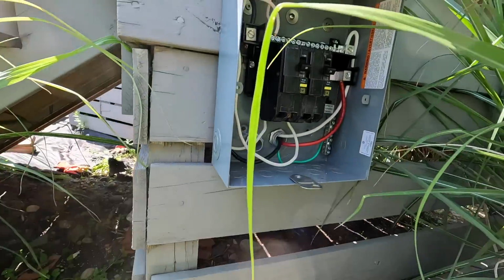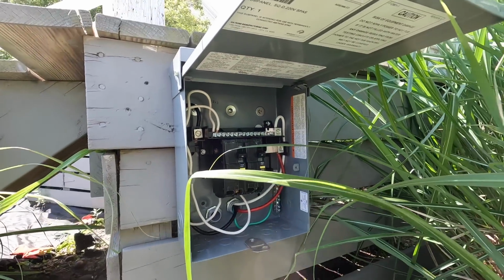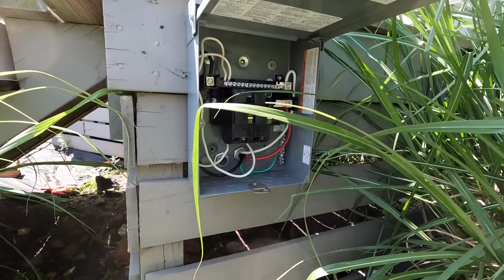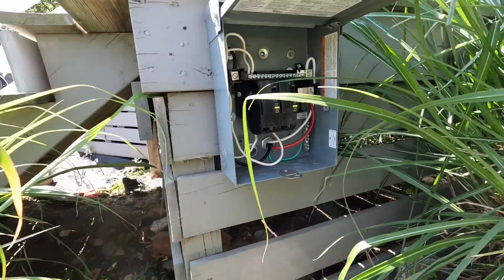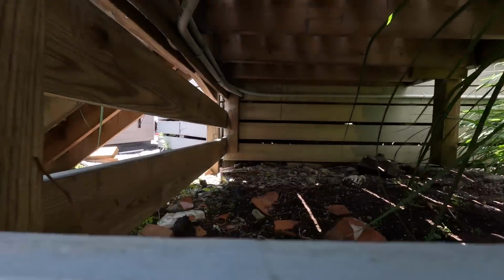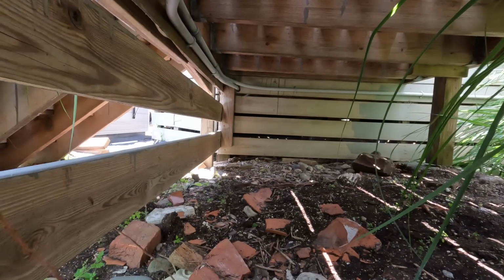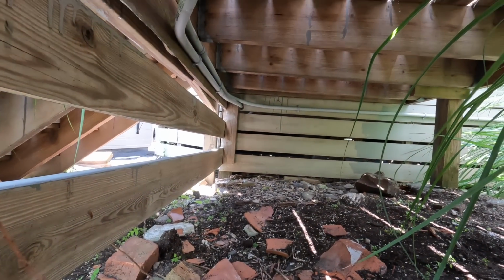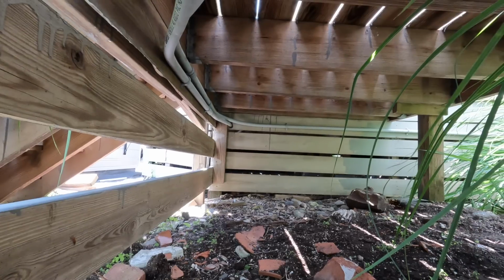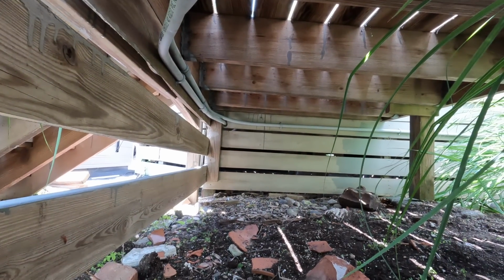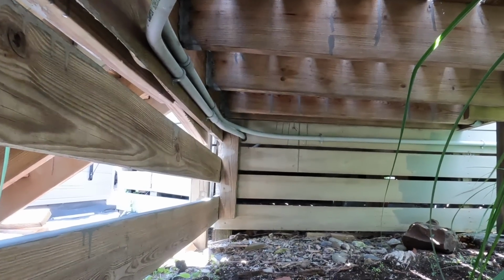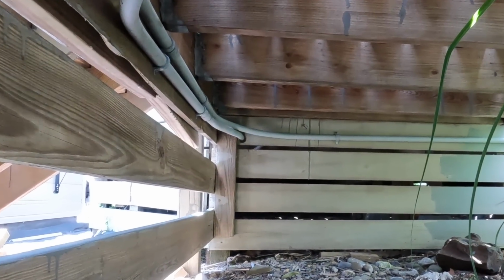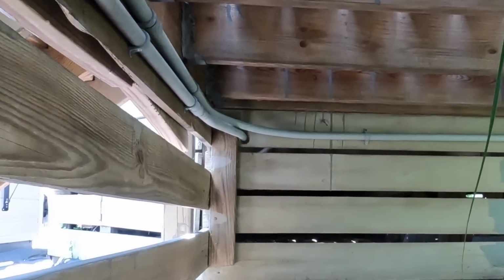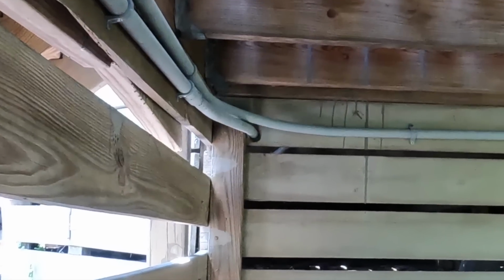Here's my main lug only panel that came with the hot tub assembly. It has a double pole 30 circuit and a double pole 20 circuit, and both of these circuit breakers are GFCIs. This is underneath the staircase. There's some of the conduit that I ran that I did not film. The lower conduit is what goes to the hot tub, and the one up on the top is what feeds the sub panel from the 200 amp sub panel in the basement.